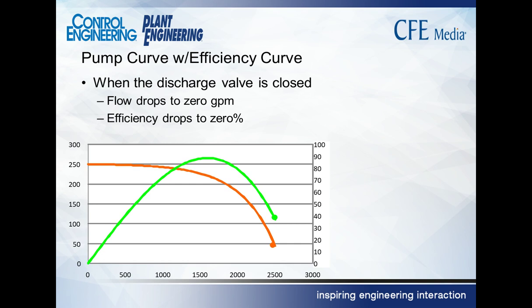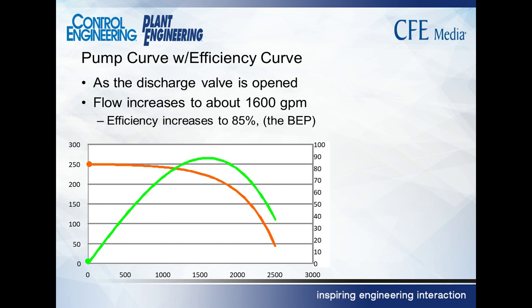Now, that makes sense to everyone, I hope. If I've got 0 flow at that point, the discharge valve is completely closed. The pump's still running. I'm putting energy into the pump, but I'm getting nothing out. The efficiency is 0. As I open the discharge valve and flow begins to go through the pump, the efficiency has to increase. I'm beginning to do some work. And it will continue to increase as I increase the flow until it gets to the point that we call the best efficiency point, the BEP.